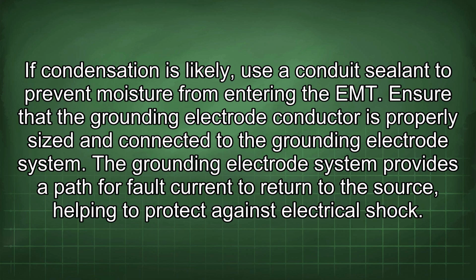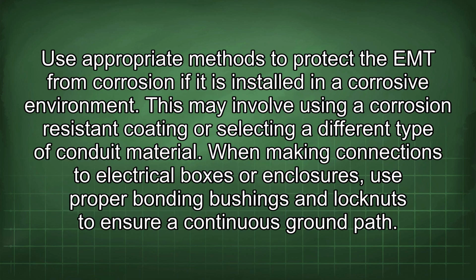Ensure that the grounding electrode conductor is properly sized and connected to the grounding electrode system. The grounding electrode system provides a path for fault current to return to the source, helping to protect against electrical shock. Use appropriate methods to protect the EMT from corrosion if it is installed in a corrosive environment. This may involve using a corrosion-resistant coating or selecting a different type of conduit material.